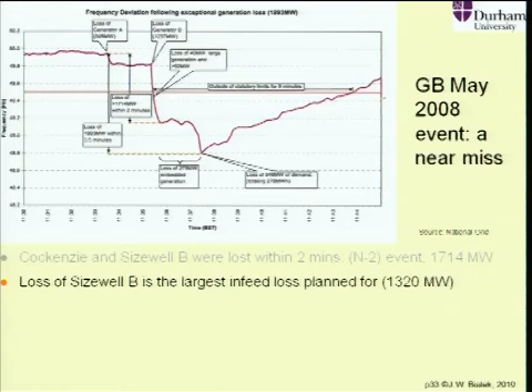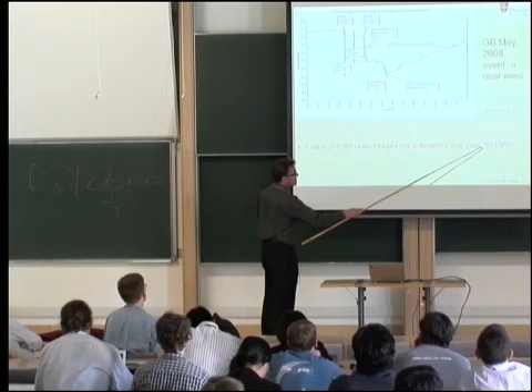That means we were bound to have some problems, and the situation was made even worse, because due to the dropping frequency, nearly 300 megawatts of wind tripped on low frequency. There's a long story about it, but basically wind generators are sensitive to frequency, and if the frequency goes too low, they trip. So nearly 300 megawatts of wind tripped, and this is this third drop of frequency over here. So you can see a drop of frequency from 50 hertz to 48.8 hertz, and a total of nearly 2 gigawatts lost.